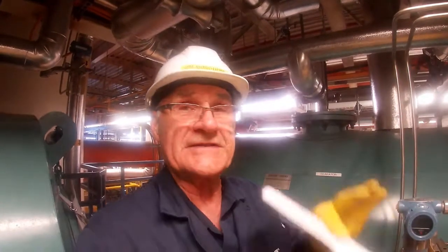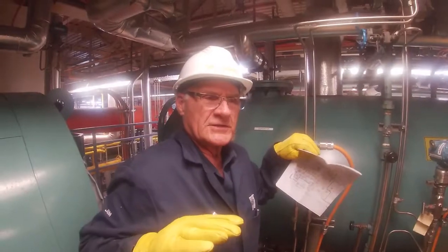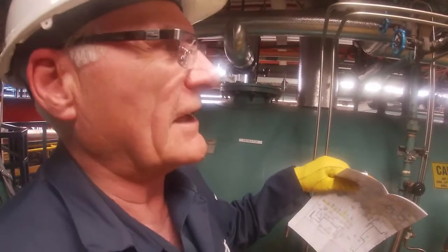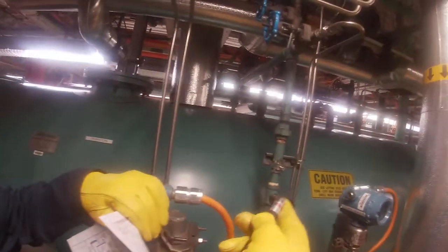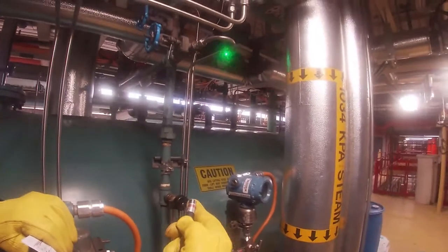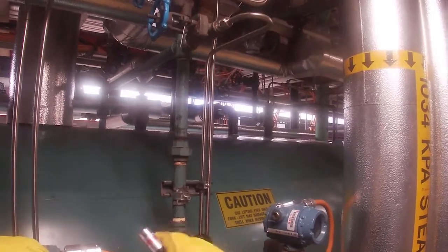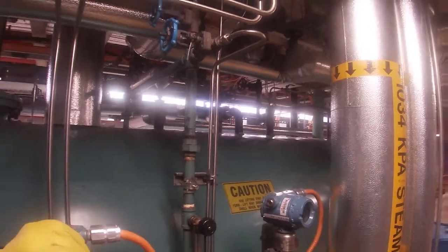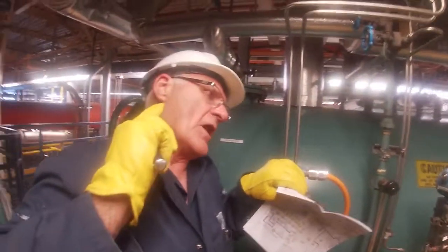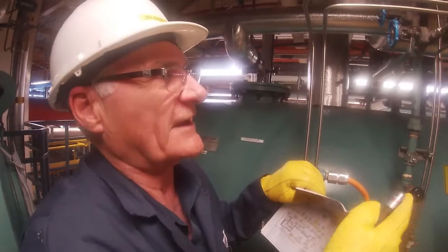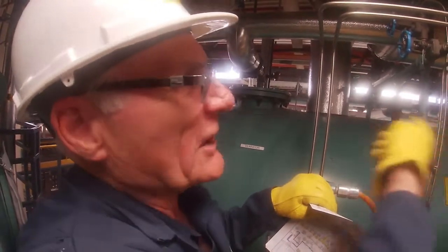So now we're going to go downstairs and take a look at the pumps. Before we go downstairs to look at the feed water pump, one remaining thing that I just thought of: we've got a freshwater makeup valve right here. That automatic control valve is part of the split range circuit that looks after this. If they can't get enough water out of the hot well, then that valve opens up at about 40% output signal and starts to add fresh water makeup.